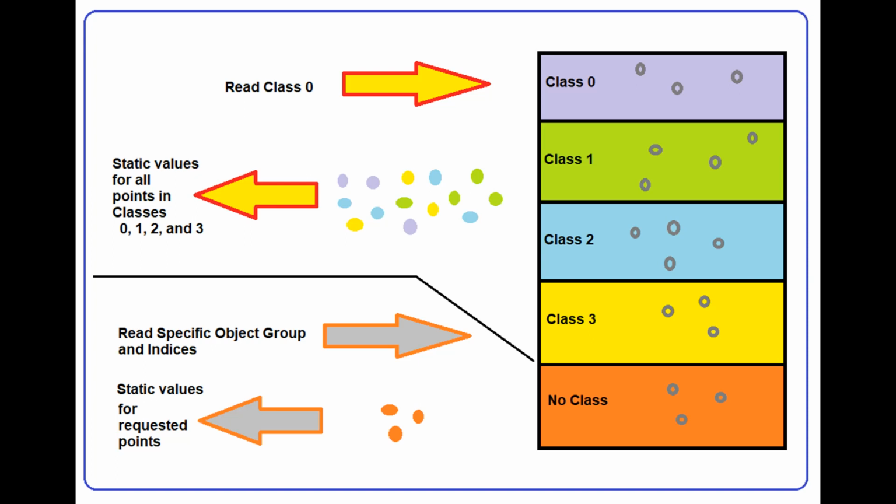Being reported once is enough. Such an outstation can assign the last 32 analog inputs, the parameters, to no class. Points assigned to no class are not returned in a class 0 data poll and never generate events.